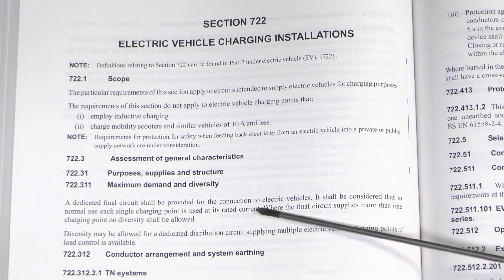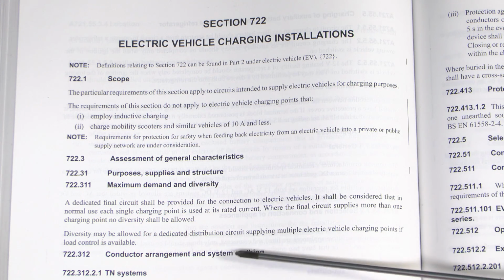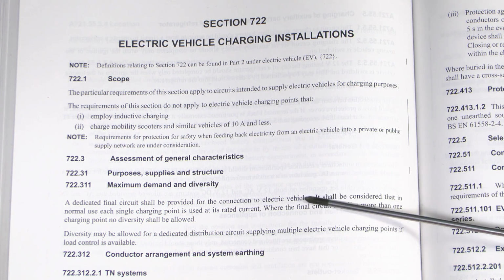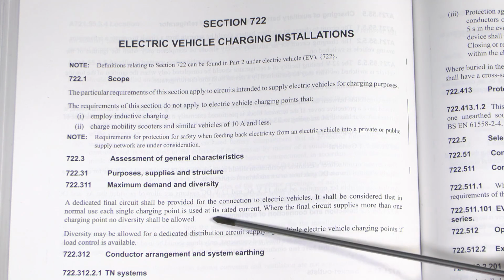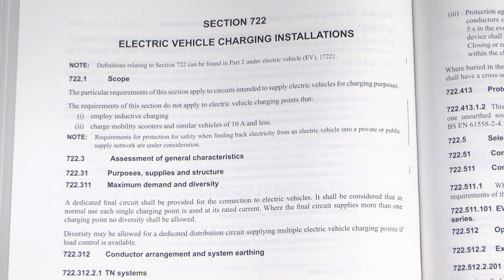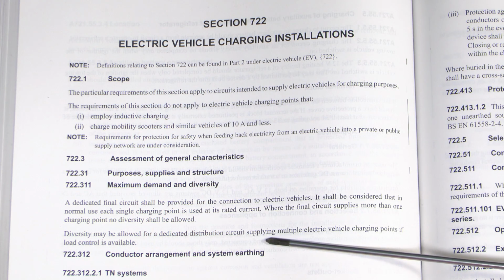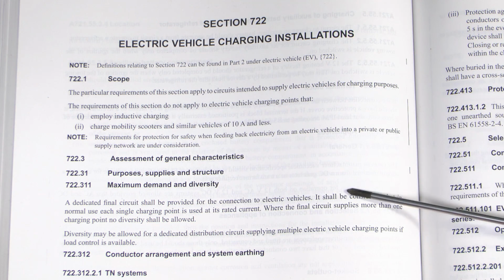And again, it's not something that's like a cooker or something where, although it's got a 32 amp circuit, the current drawn is usually considerably less. It's definitely the case that when it's plugged in, it's using the power, and that's all there is to it. So in that regard, it's similar more really to things like an electric shower, which of course when it's turned on, it's using the full load current 100% of the time.